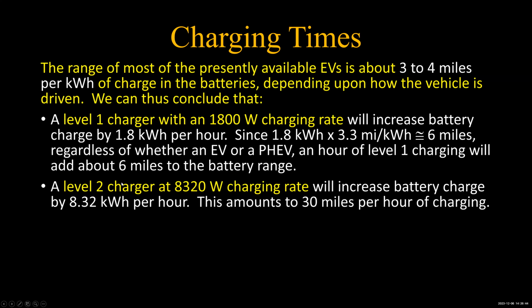All right, here's level 2 at 8,320 watts. Why 8,320? Well, if you divide 8,320 by 240, it comes out to an interesting number. 8,320 divided by 240 just happens to be 35 amps. Now, that's divided by 240, but if you divide it by 208, which is typical in a lot of bigger buildings, it comes out at exactly 40 amps, which means that you have to multiply that by 125% for your wire sizing and your overcurrent protection. In other words, you use a 50 amp charger on this.